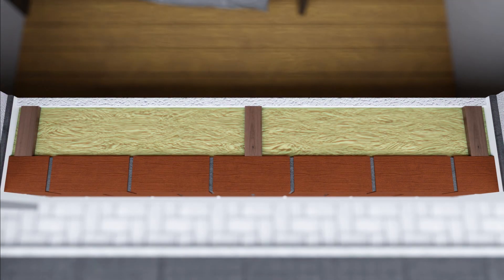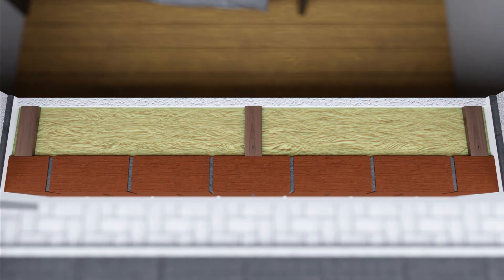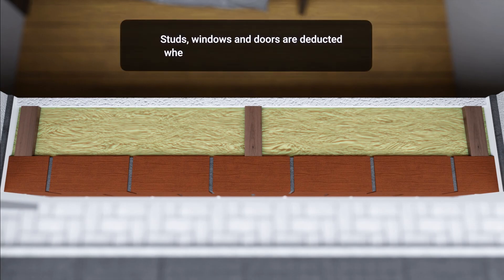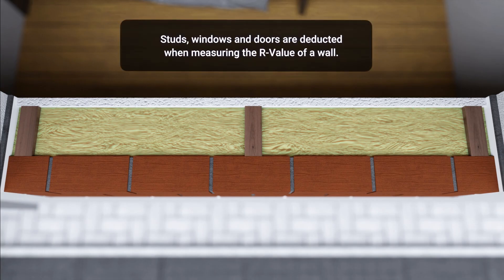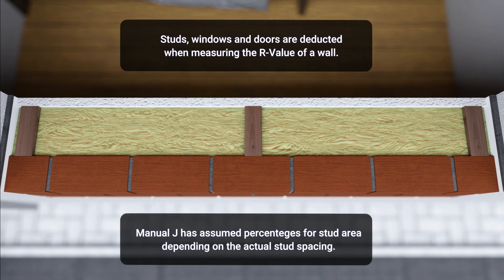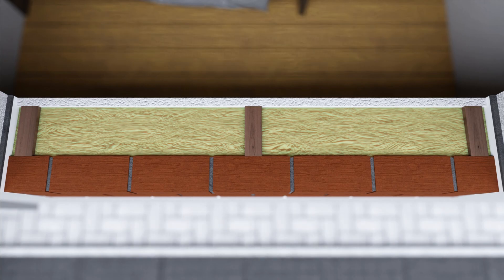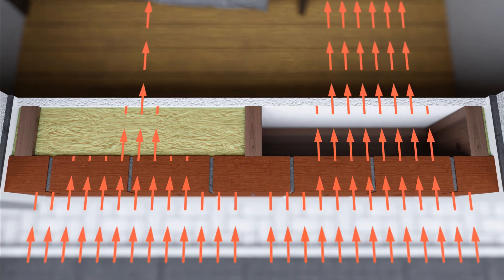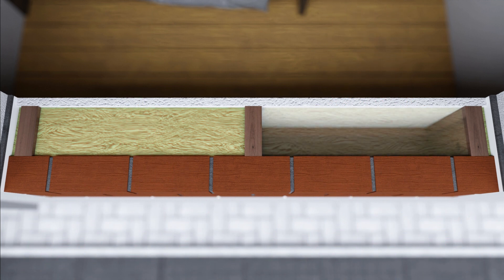The insulation is located between the studs. When calculating the R-value for Manual J, you'll need to consider the wall, insulation, and studs. You'll need to deduct the studs as well as any windows and doors when measuring the R-value of a wall. Manual J has assumed percentages for stud area, depending on the actual stud spacing. An ACCA-approved software will calculate this for you. A wall without insulation will have a lower resistance, or R-value, than a wall with insulation, and the rate of heat transfer via conduction is significantly higher in walls that lack insulation.